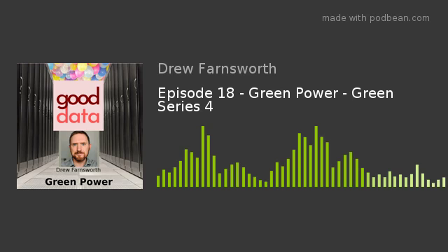Now, going up the line, how do you get the utility power to that UPS? So on a very large facility, there tend to be a lot of transformation steps for power. You tend to have, let's say, 69 kilovolt power coming to the campus. That has to get transformed down usually to 480 to go to the UPS. And then the UPS, somewhere down the line, transforms that down to 208, 120 to get to the servers themselves.